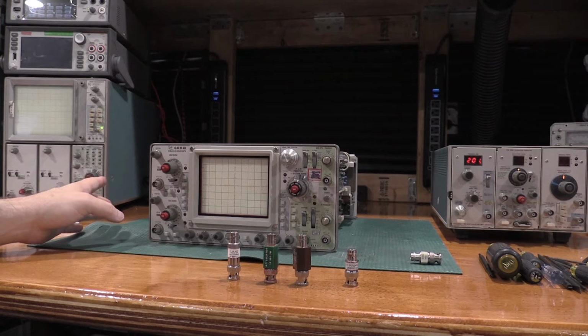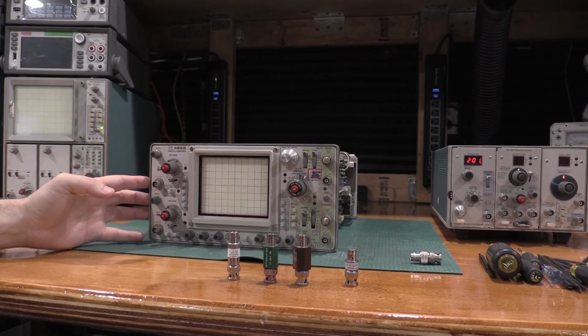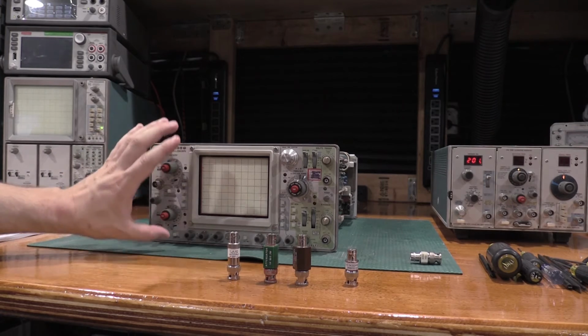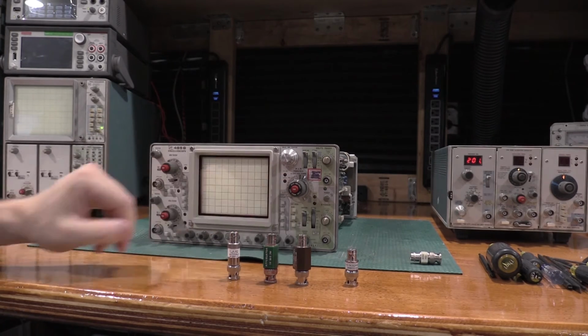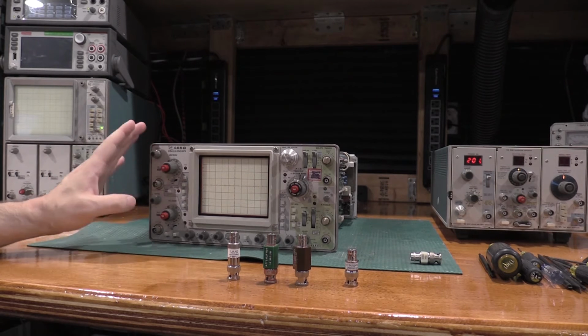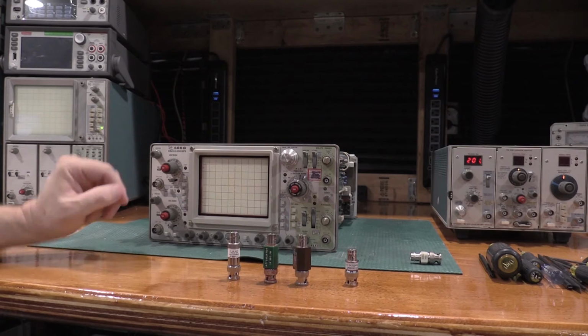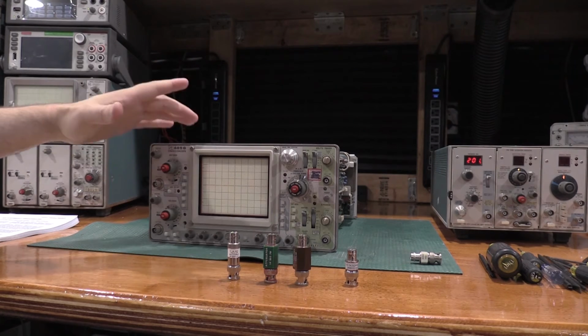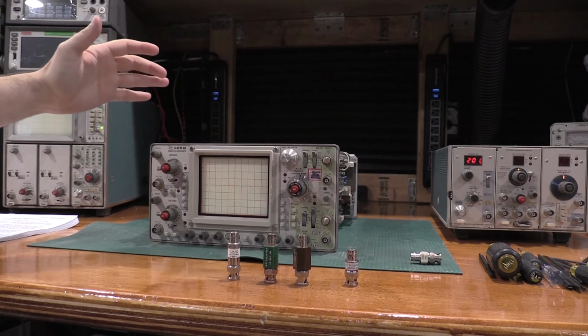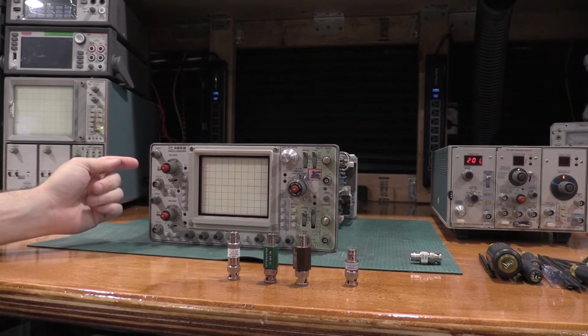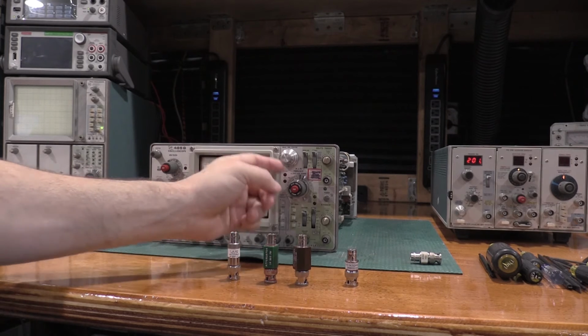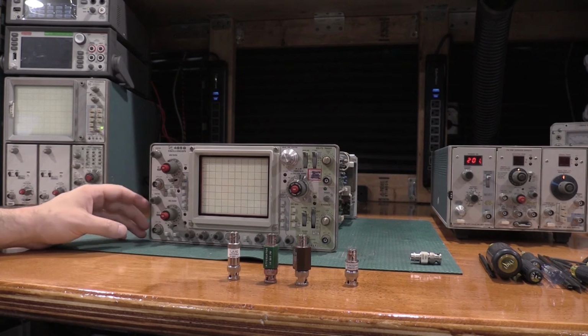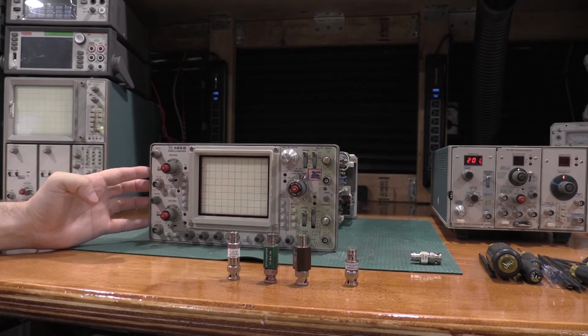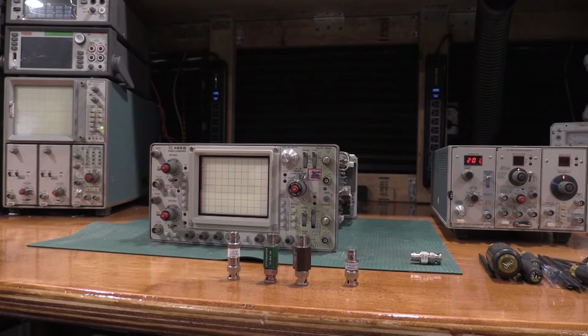When I was doing the 7000 series scopes, I was able to split it up into 3 videos: doing the frame itself, doing the vertical section, and doing the time base. Because this is a 400 series, to do the full calibration on the instrument, we have to do all of them. So we'll start with essentially the frame, power supply, tube, get all of that lined up. Then we'll go into the vertical. Then we'll go into triggering. Then we'll go into time base and the timing. So it's going to be a long video. Unfortunately, there's not much I can do about that. It's just a long calibration procedure. So sit back, relax, and let's bring one back to life.